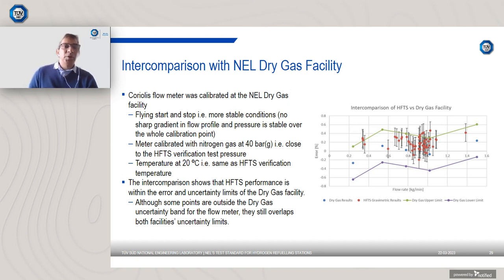The pressure at which the flow meter was calibrated was also constant at 40 bar. But what the intercomparison test results essentially show is that the performance of the hydrogen field test standard is within the error and uncertainty limits of the dry gas facility, and therefore both test facilities do meet their target uncertainty.